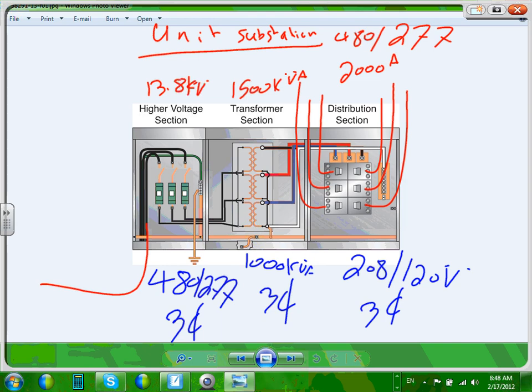Every time you hear them talking about a unit substation, they talk about three things: a high voltage section, a transformer, and low voltage. Now, the high voltage could be as high as 13.8 kV or as low as 480. The transformer could be 2,000, 1,500, all the way to 500 kVA, any size. The secondary side most likely can be 480/277, or 208/120 if you're bringing in 480/277.